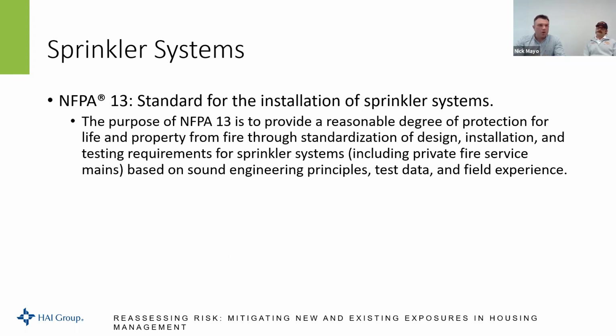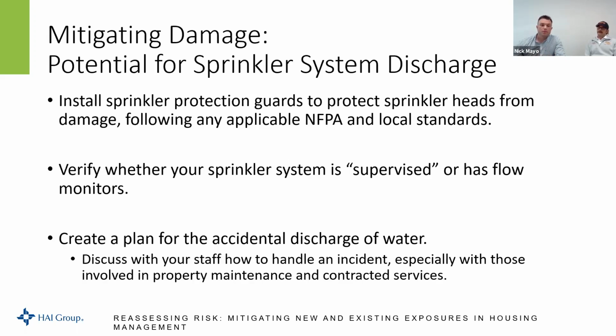So again, depending on how old your building is, whether it's existing construction, new construction, or you're retrofitting, NFPA 13 will be the standard that fire marshals like Paul would reference in regards to either the install, upkeep, and maintenance of a sprinkler system in your building. So in regards to mitigating damage and the potential for sprinkler system discharge, you can install sprinkler protection guards to protect the sprinkler heads from damage, following any applicable NFPA and local standards. If your sprinkler heads are exposed and you can see them, there are guards available so that, God forbid someone hits a sprinkler head, it won't activate. You just want to make sure that they're installed so that the sprinkler head still operates properly and as efficiently as it was designed to operate.